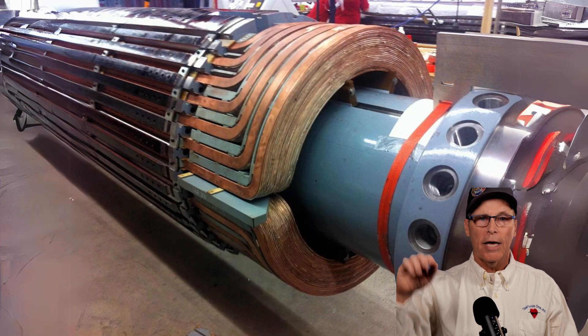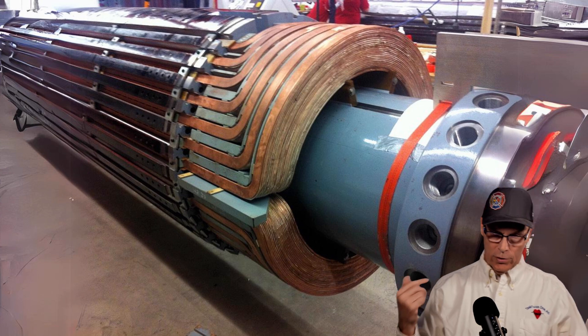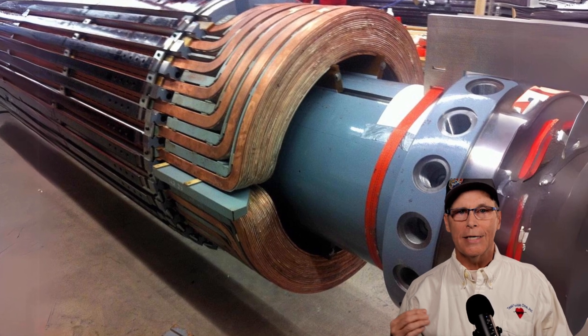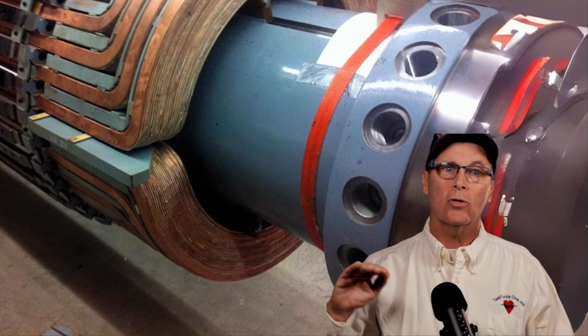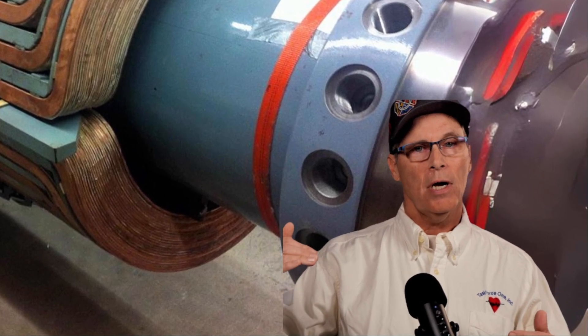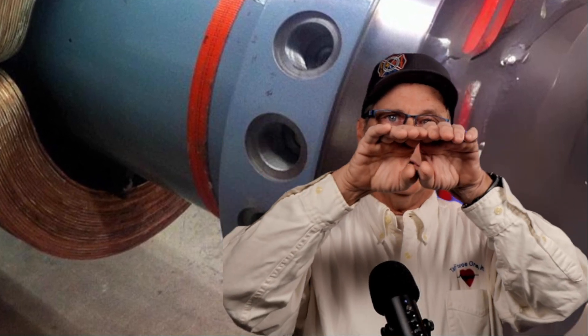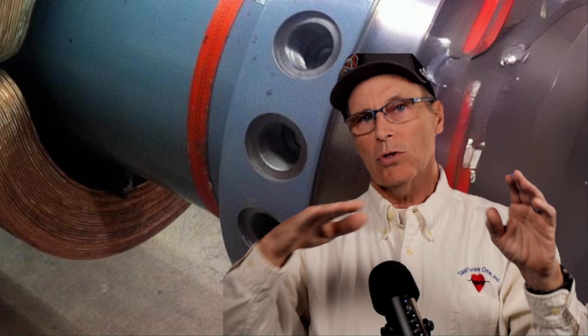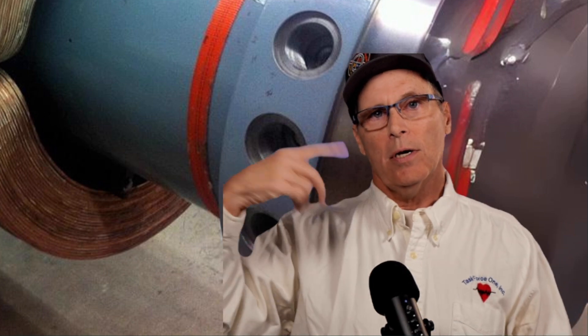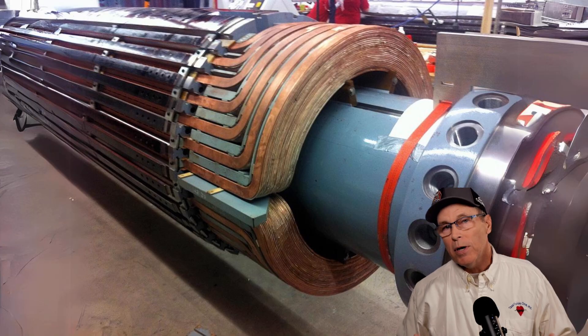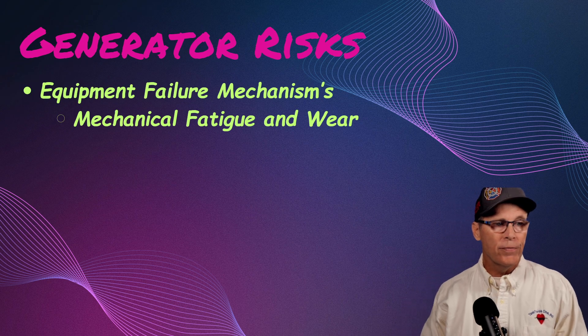You can see how close those bars are together — you don't want them touching. That becomes a short circuit, and electricity takes that path of least resistance. As electricity flows, so does heat. The electricity builds up heat on one side, and since it's not flowing on the other side, we see deformation — the warm side gets longer and the cool side shorter, so the rotor bows. As load goes up, vibration gets worse. If vibration follows the load, that's an indication of a shorted end turn.